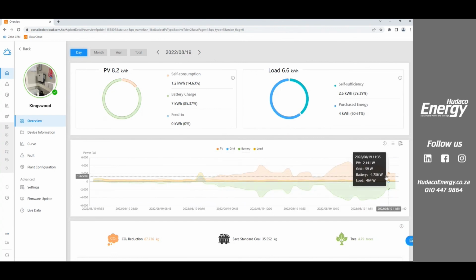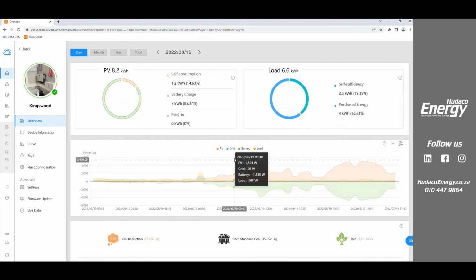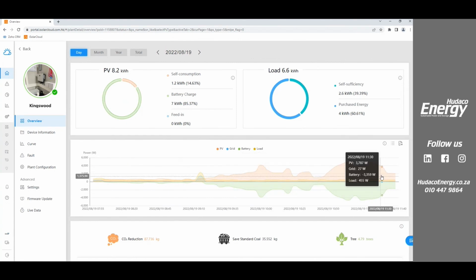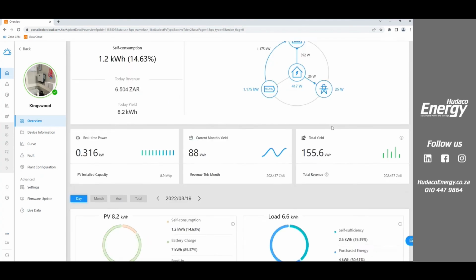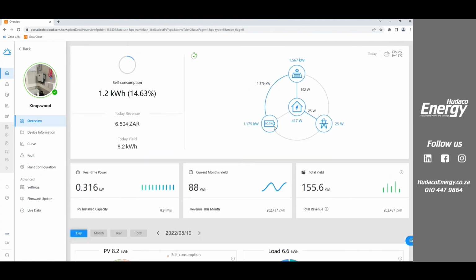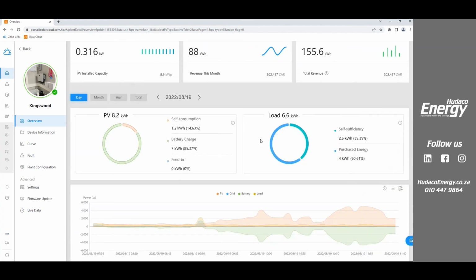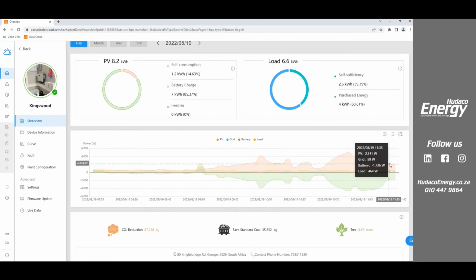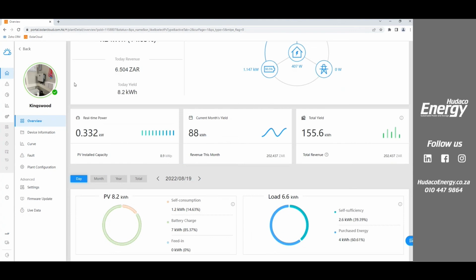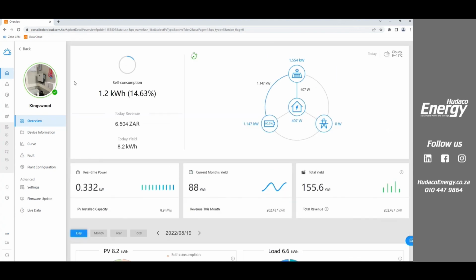The batteries, however, have probably reached, let's say, an 80 or 90% mark, and we've gone from bulk into absorb phase. So if anybody's familiar with the battery charging phases, there's bulk, absorb, and then float. So we've done the bulk, we're now in absorb, which is a smaller amount. You see that would have happened at about 95, and now it's just going to push 1 kilowatt in for probably the next hour or so, maybe hour and a half as it goes through. Okay. So any questions on this?